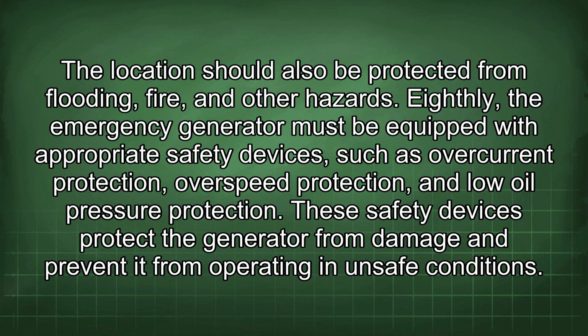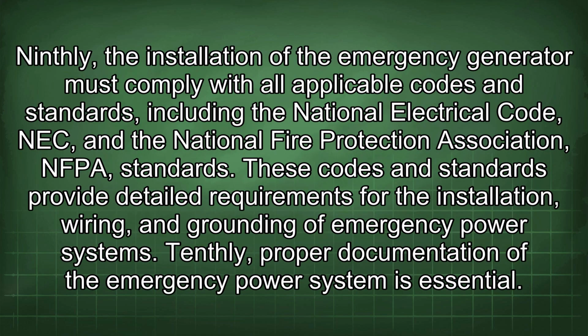Eighthly, the emergency generator must be equipped with appropriate safety devices such as overcurrent protection, overspeed protection, and low oil pressure protection. These safety devices protect the generator from damage and prevent it from operating in unsafe conditions. Ninthly, the installation of the emergency generator must comply with all applicable codes and standards, including the National Electrical Code, NEC, and the National Fire Protection Association, NFPA, standards. These codes and standards provide detailed requirements for the installation, wiring, and grounding of emergency power systems.